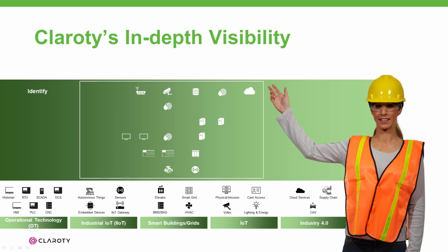Whether passive asset detection or active asset detection are used, CTD starts by identifying the hardware assets that make up the system. The process of identifying hardware assets includes gathering advanced details and metadata from each device. CTD then uses the incoming data to build a detailed hardware database. In the process of sniffing communications traffic between hardware assets that are part of the system, CTD also logs the type and direction of communication between all hardware assets that do communicate. This allows CTD to build a detailed map of the physical network.